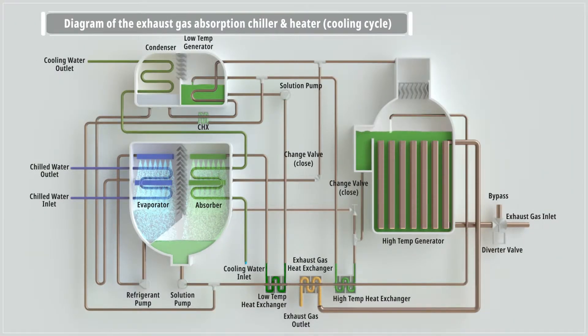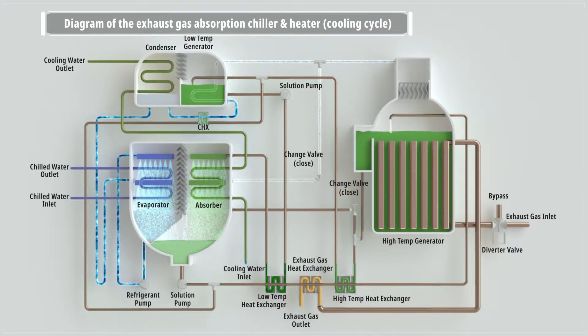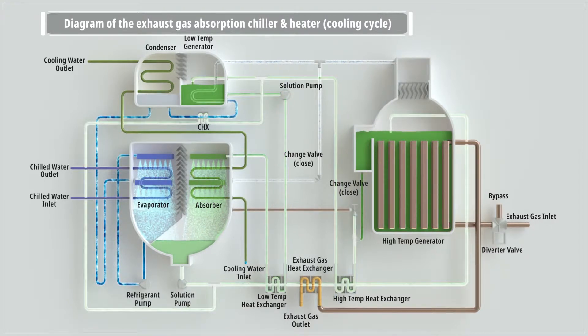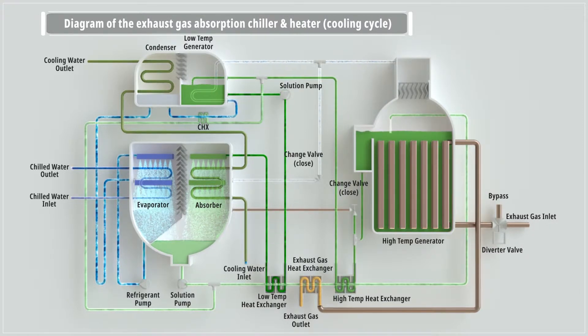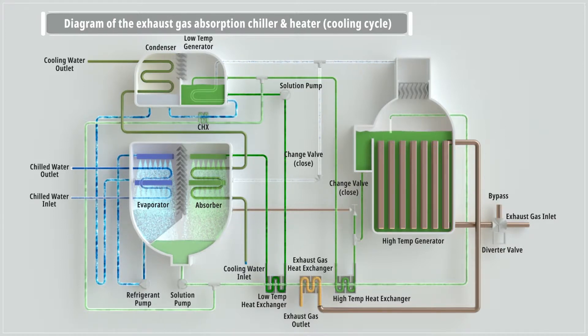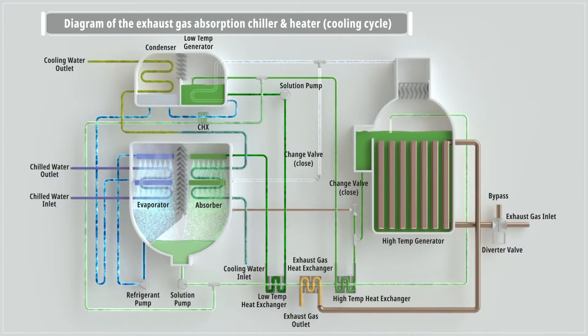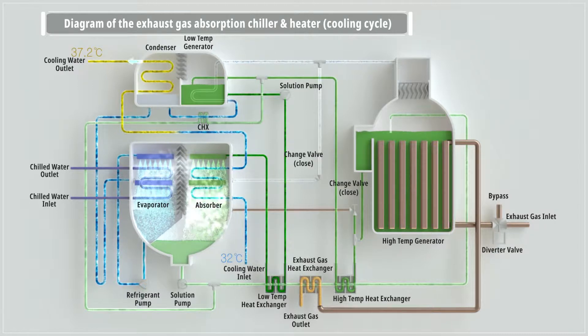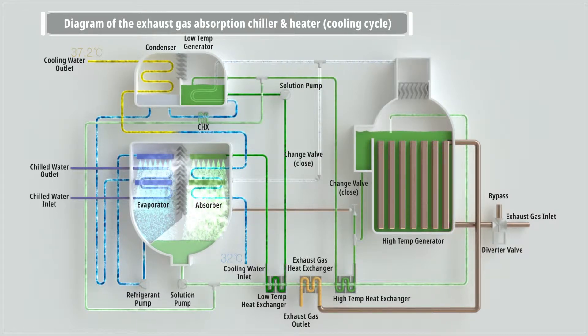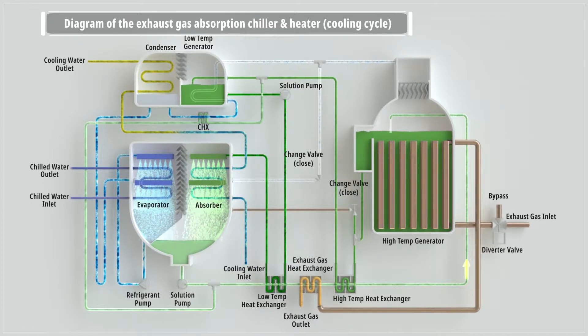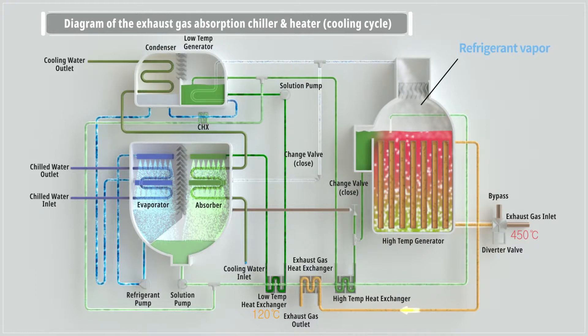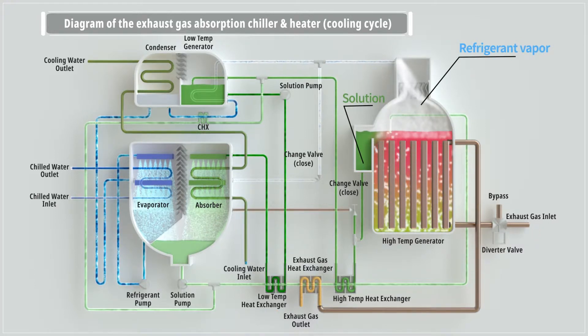Inside the CHP chiller, the refrigerant that cools down the inlet water is circulated by LiBr solution. After being used in cooling, heated chilled water flows through to the evaporator where the refrigerant evaporates and chilled water returns to the system. Vaporized refrigerant flows through to the absorber where it is mixed with the LiBr solution. The diluted solution from the absorber flows to the high temperature generator, where it is heated by exhaust gas heat, separating into refrigerant vapor and LiBr solution.